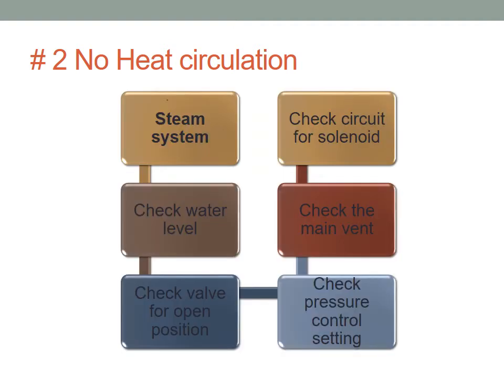Steam system. Again, we say steam is still very common in this area. And what could be the problem with steam? First off, water level. We have a low water cutoff. If it's low, it's not going to run. So make sure we have enough water in the system. If not, make sure that you fill in some water.